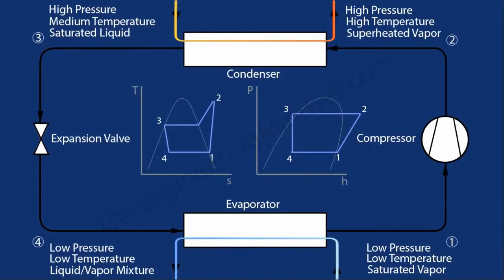As with all the expansion valves featured in this video, you can see here the performance. So the expansion valve is located just here on the chart. So that is going from 3 to 4, and that means the refrigerant is going to change from a high pressure to a low pressure, from a medium temperature to a lower temperature, and it's going to go from a saturated liquid to a liquid vapor mix. And you can see this on the chart. So if you're looking at the pressure axis, you can see there's a decrease in pressure. There is a decrease in temperature. There is also an increase in entropy, but a consistent enthalpy.